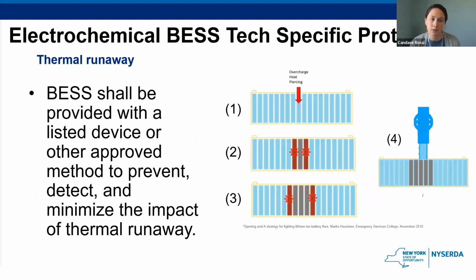So coming back to thermal runaway, which has been woven through this presentation, once thermal runaway is started, it cannot be stopped. So energy storage systems should have a device that can recognize when the temperature is rising, and the device should isolate that area and send a signal to the owner of the system that there is a problem. Data testing has shown that stopping the charging and discharging of a cell is an effective measure to prevent a cell from going to thermal runaway.